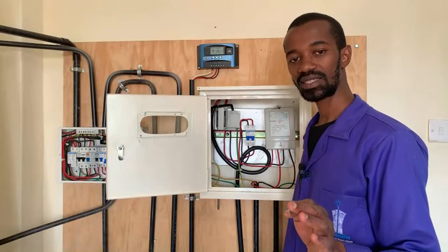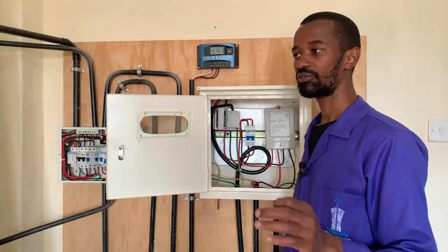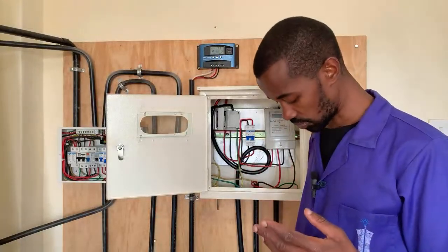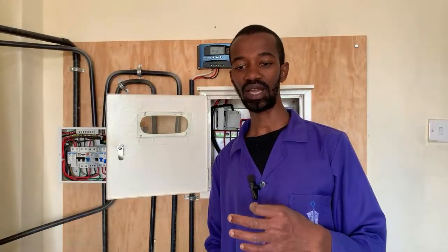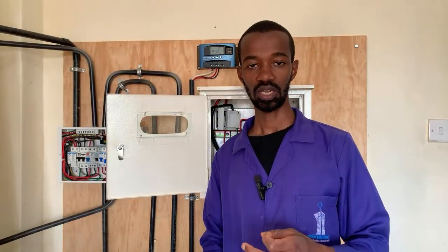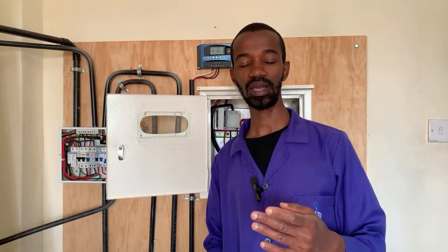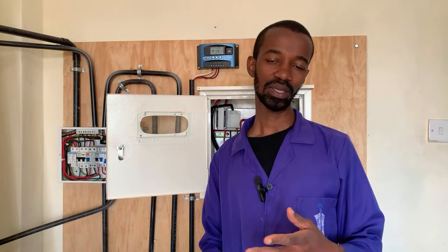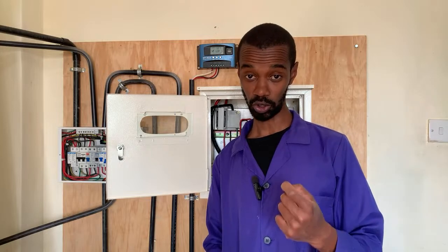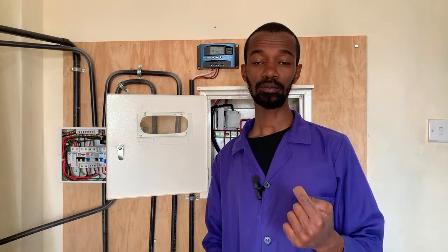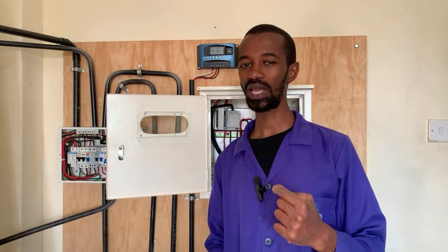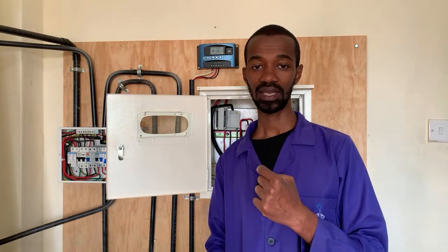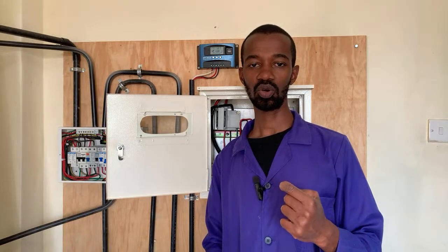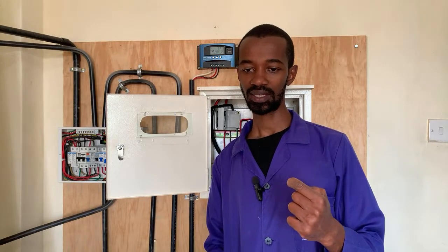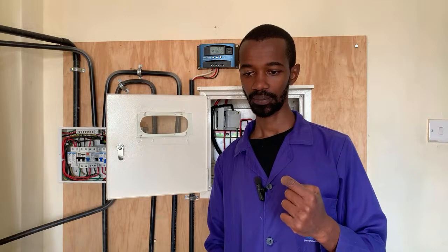We might start with that. If they are receiving an electric shock in the bathroom, they could not necessarily be receiving one in the kitchen. Simply because it is the same electrical installation doesn't mean the entire installation is faulty. We will be tempted to go that route, but since we are still at the meter box before we progress, let us exhaust that level first. So at the meter box, what do we expect?